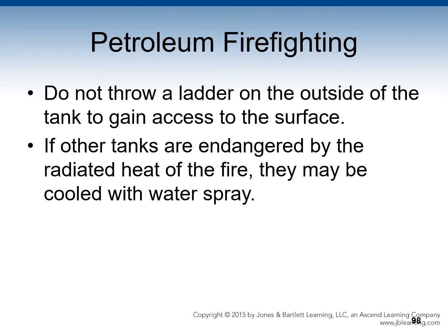Throwing a ladder on the outside of the tank to gain access to the surface is extremely dangerous and not recommended. If other tanks are endangered by the radiated heat of the fire, they may be cooled with water spray. The water must be applied directly onto the tank shell. Setting up a water curtain to absorb radiated heat in the air is ineffective.